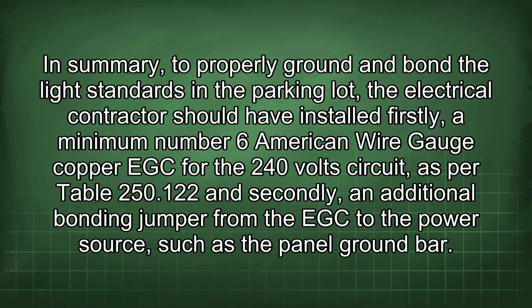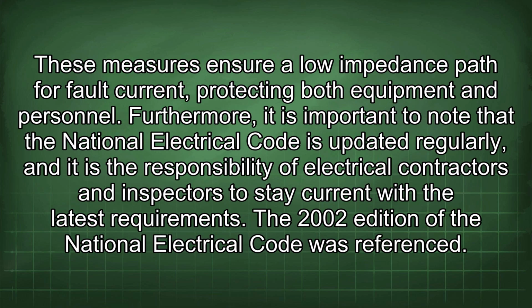In summary, to properly ground and bond the light standards in the parking lot, the electrical contractor should have installed firstly a minimum number 6 American wire gauge copper EGC for the 240 volt circuit as per Table 250.122, and secondly, an additional bonding jumper from the EGC to the power source, such as the panel ground bar. These measures ensure a low impedance path for fault current, protecting both equipment and personnel.